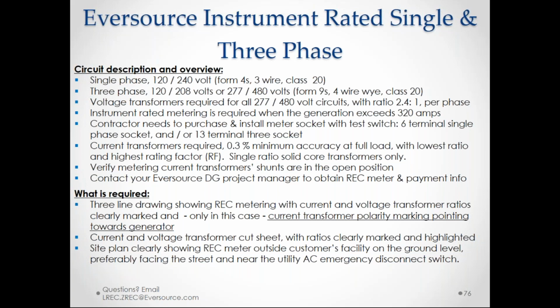And as well, that site plan that's provided should also clearly identify the proposed location of that ZREC meter, which should be ground level exterior. If we see something that is other than that, we are going to question why that is needed and decide if we will allow that on a case-by-case basis. So when you get beyond 320 amps, that's when things will need to be instrument rated. So in the case of single phase, that's a Form 4S. In the case of 3-phase, that's a Form 9S.